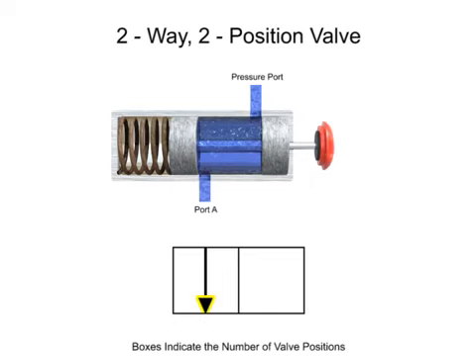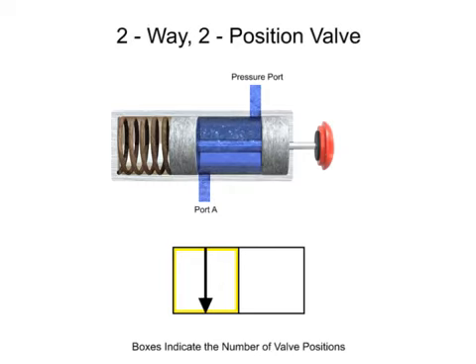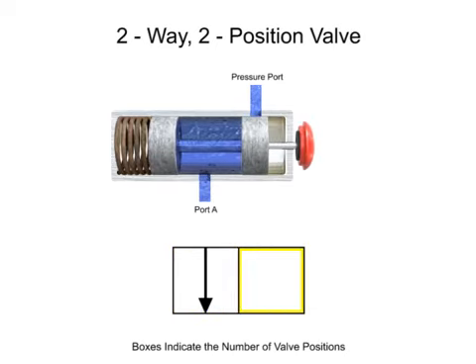A solid arrow indicates the direction of liquid flow. The first position of this valve allows fluid to flow from the pressure port to port A, so an arrow is drawn in the first box to indicate fluid flow. A T indicates that a port or way is blocked or closed. This valve's first position has no ports blocked, but its second position blocks both. Therefore, two T's are added to illustrate the lack of fluid flow in the second position.